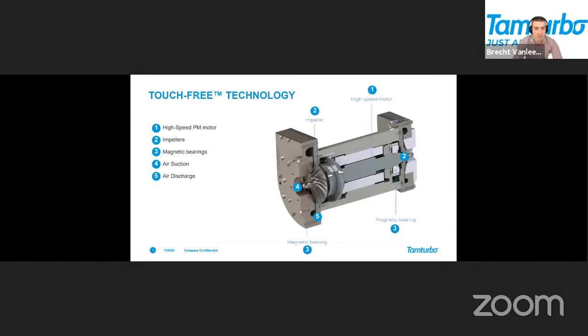Our core technology is made on a single module consisting of a permanent magnet motor, which is number 1, 2 magnetic bearings, number 3, at both sides, and 2 impellers or stages on a single shaft. The shaft is then lifted in the air by the magnetic bearings during the operation. Hence, there is no friction and no energy losses, and of course, low maintenance.